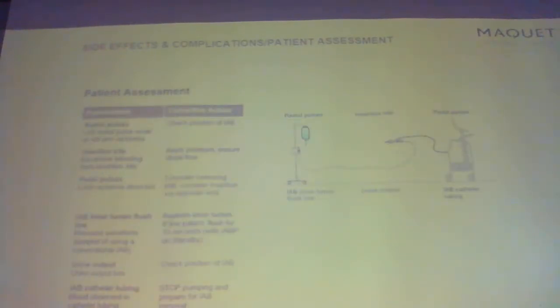Patient assessment, I talked about this. The radial pulse, insertion site, pedal pulses, intra-lumen flush line pressure waveform, urine output, blood in the tubing, corrective action, check position of the pump. We can't move the balloon, but if you notice these things, they're basically things to watch for and notify.